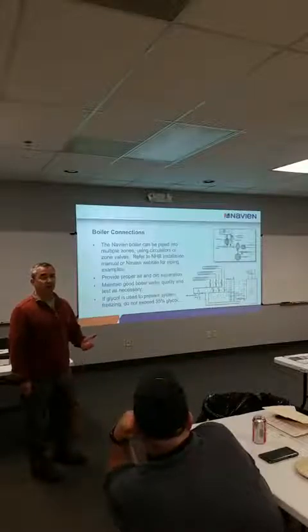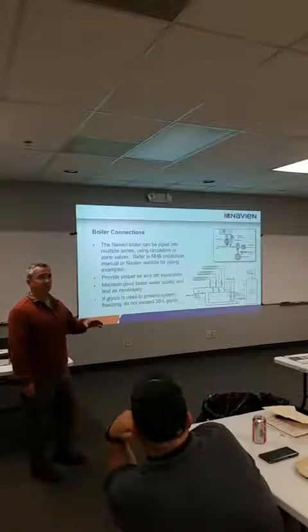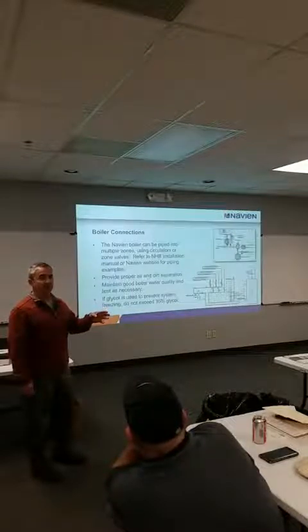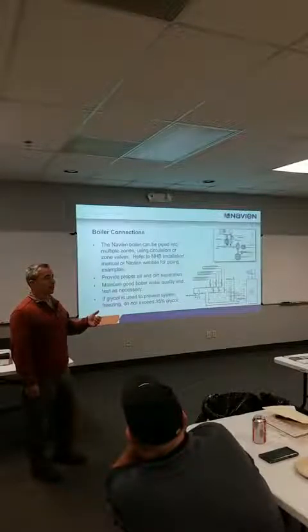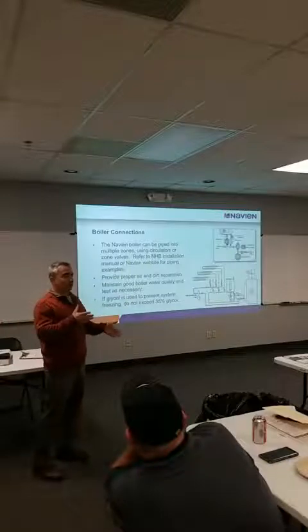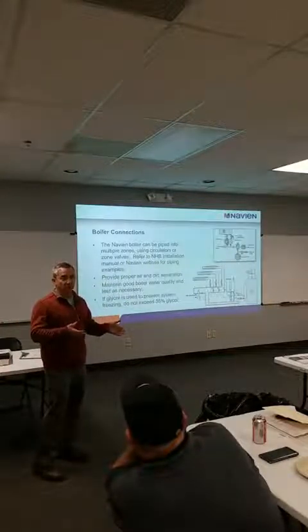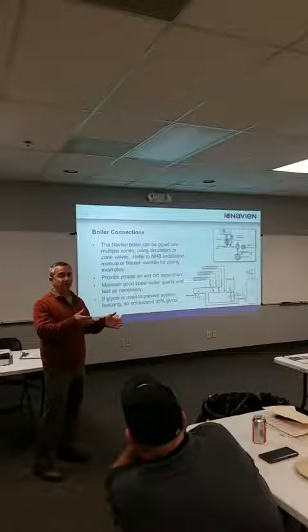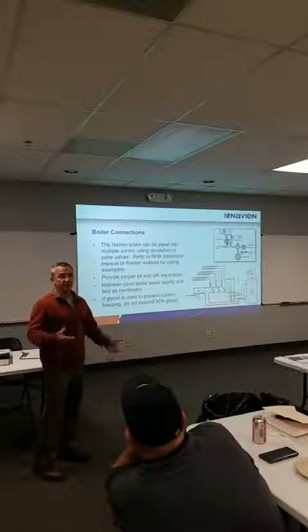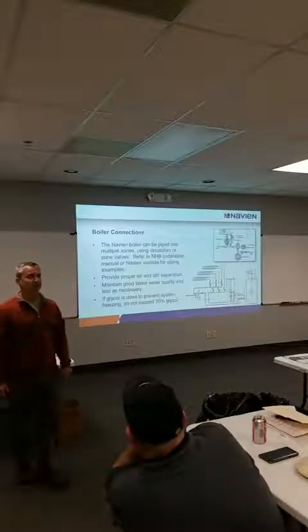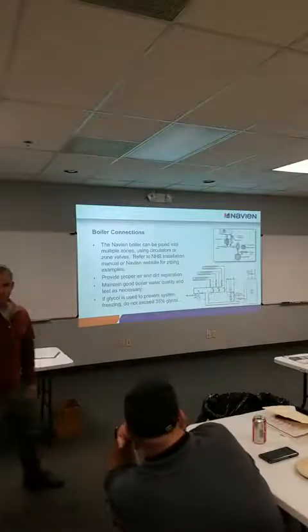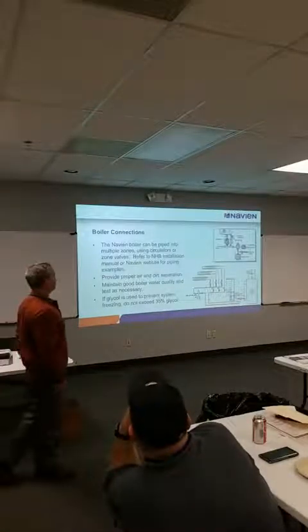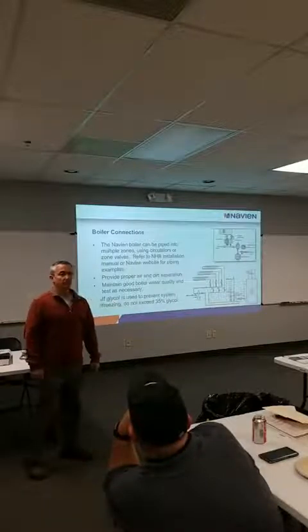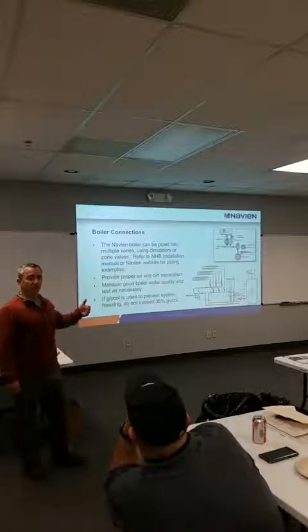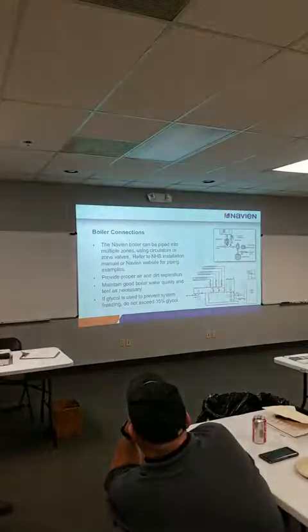Especially with the combi unit, because our pump in that combi can only get so much through that heat exchanger. So when we're sizing our combis in the water tube, our 199 unit only gives you 120,000 BTUs. Our 199 fire tube gives you 199 in, 192 out, or 187 out, something like that. So there really isn't a minimum on it. I mean, if you're 10 gallons a minute and you've got 10 gallons in the system, you're good with that. Right, correct. Because you're mixing water there regardless. Are you heating air with it, or are you melting ice with it?